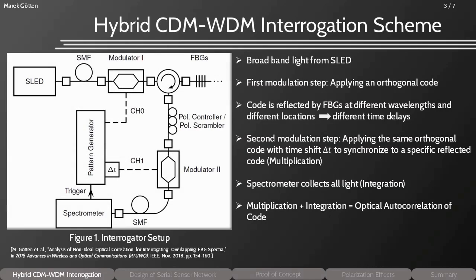In the hybrid CDM-WDM interrogation scheme, broadband light from an SLED is modulated according to a specific code sequence. This modulated light enters the sensor network via the circulator. In the network, each FBG reflects this code. Due to the different locations and different optical path lengths, all codes arrive with a different time delay at the second modulator. This modulator is driven with the same code but shifted in time. The time shift can be used to synchronize to a specific code reflected by an FBG, which can ideally pass the second modulator and reach the spectrometer.